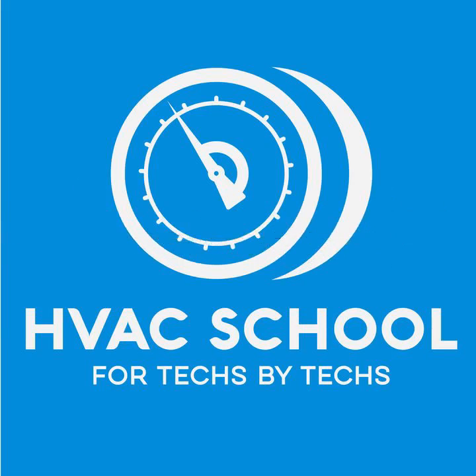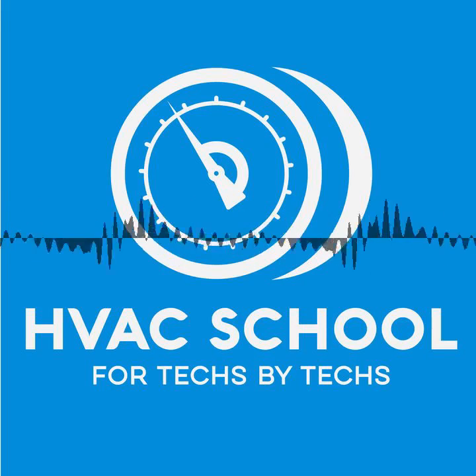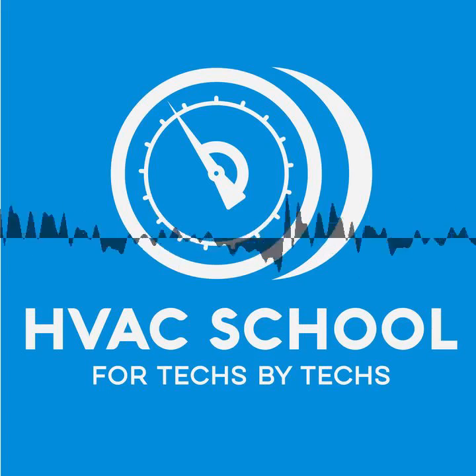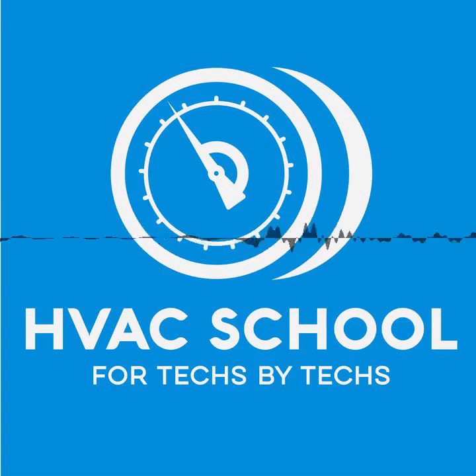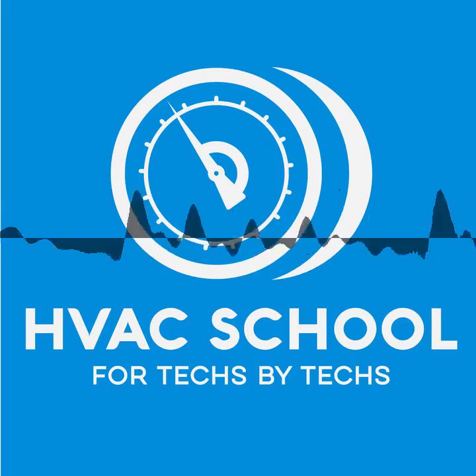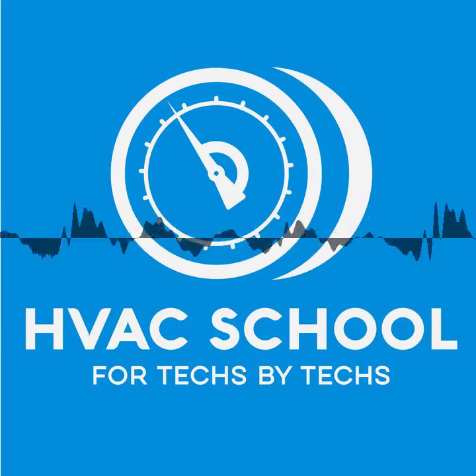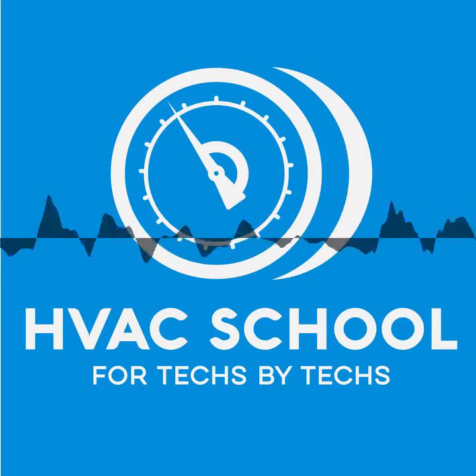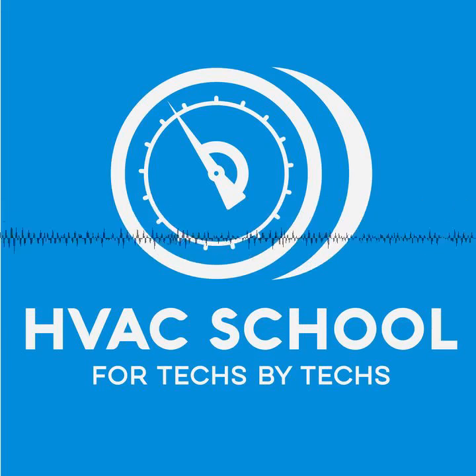Absolutely, 100%. And then you move on to ECM, and ECM just kind of ups the ante, because now an ECM motor has the ability to, on the fly, make adjustments to airflow based on some sensor input. Sensor input most commonly being dehumidification or equipment staging. So you have multiple stage equipment. It can affect the inputs and tell the motor, all right, this is the CFM that we need to produce, and make those changes on the fly.